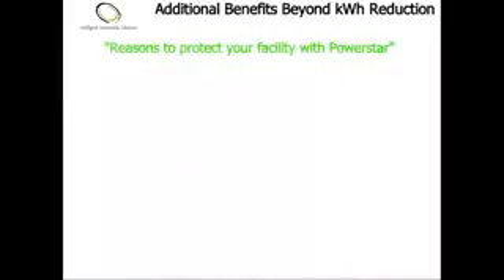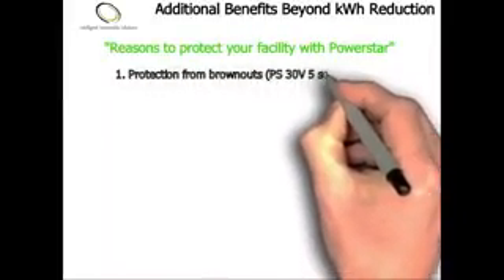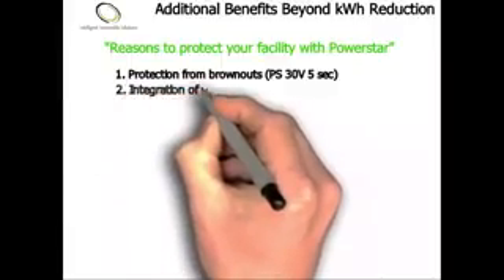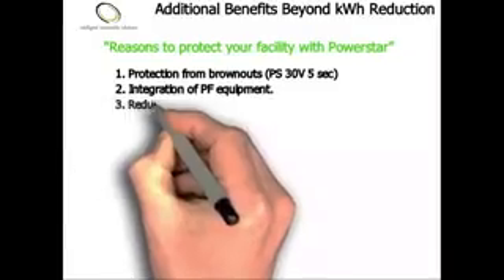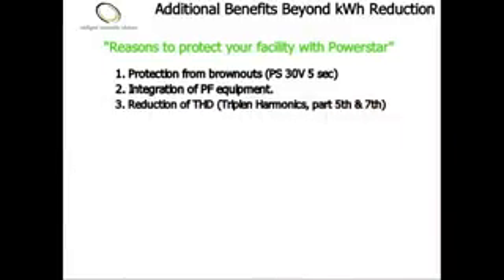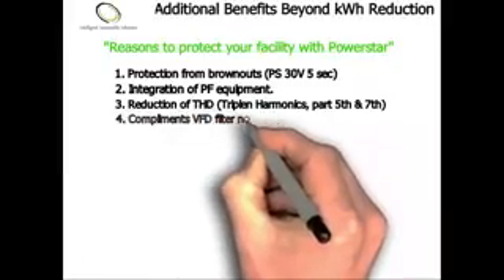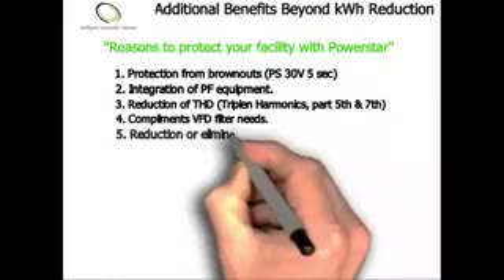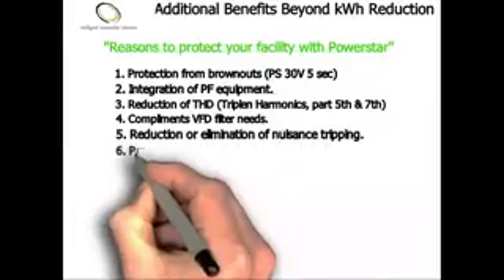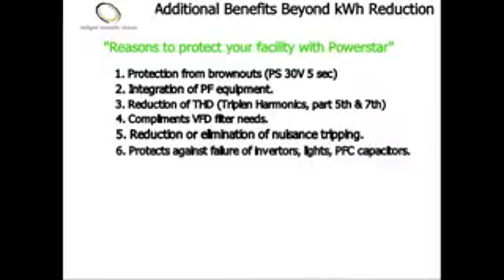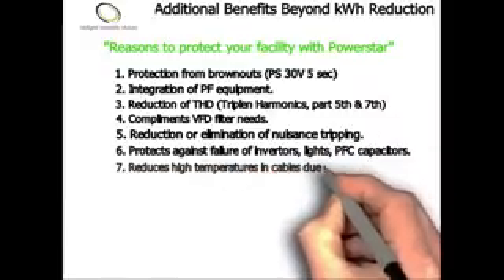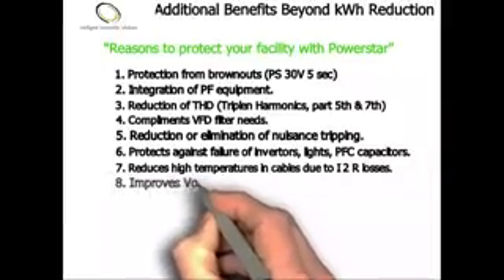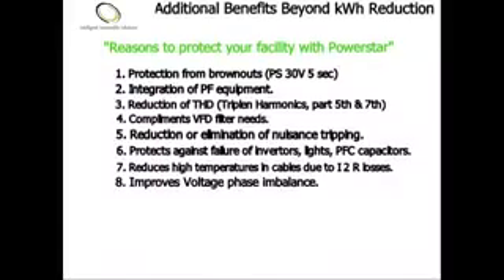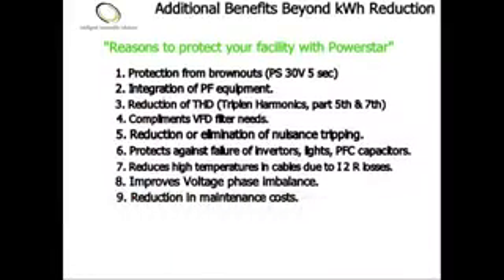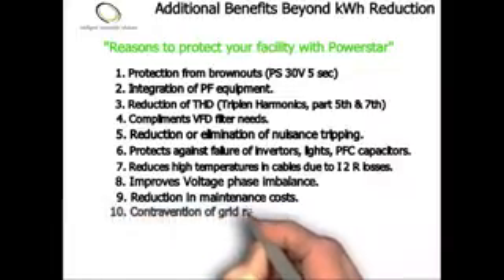Additional benefits beyond kilowatt-hour reduction and reasons to protect your facility with PowerStar are as follows. Protection from brownouts. PowerStar can maintain performance when voltage dips as low as 30 volts comfortably for 5 seconds. Helps improve the power factor and can complement power factor correction equipment already or about to be installed. Reduction of total harmonic distortion, all triplen and part 5th and 7th. Complements VFD filters and helps protect against shaft grounding. Reduction or elimination of nuisance tripping. Helps protect against failures of inverters, lights, and PFC capacitors. Reduces high temperatures in cables due to I²R losses. Improves voltage phase imbalance. Reduces maintenance costs. Can also help the contravention of grid regulations.